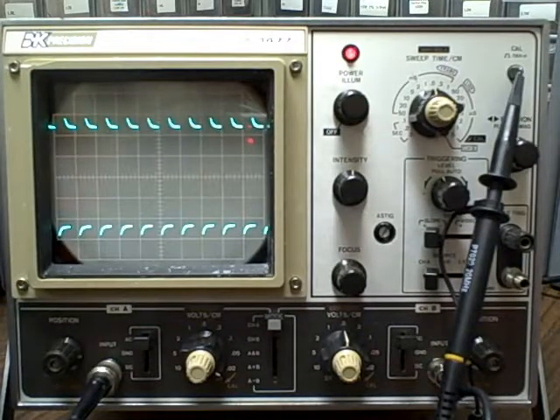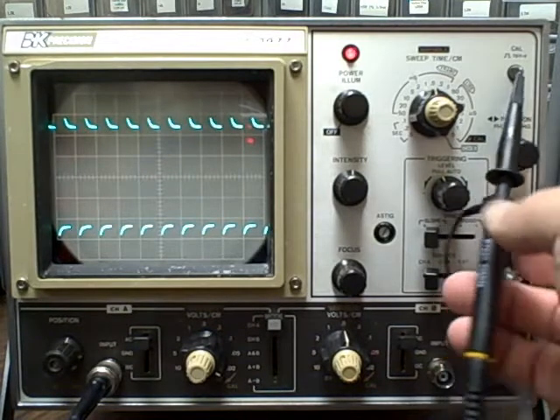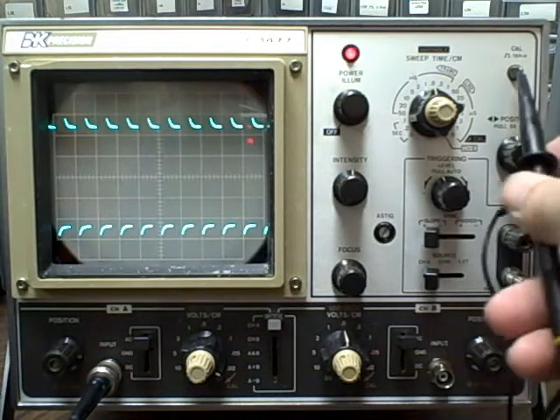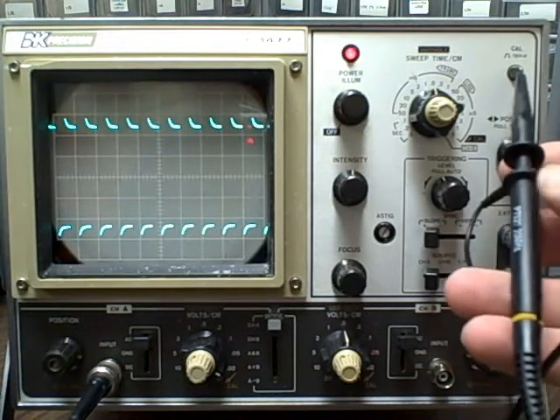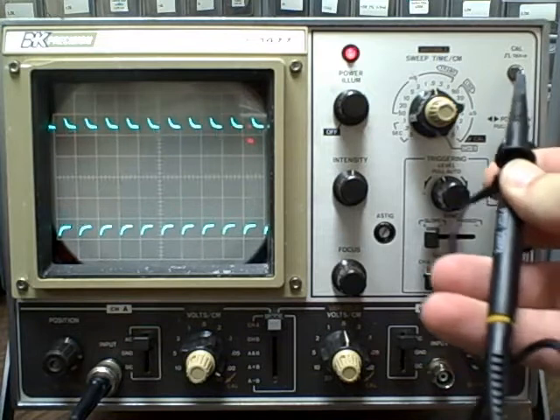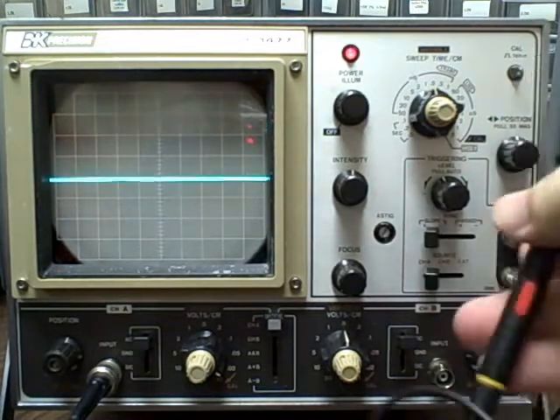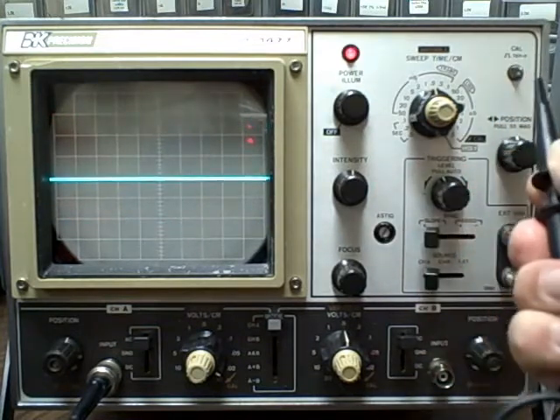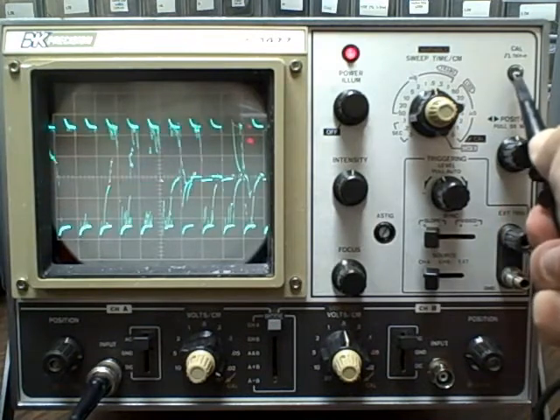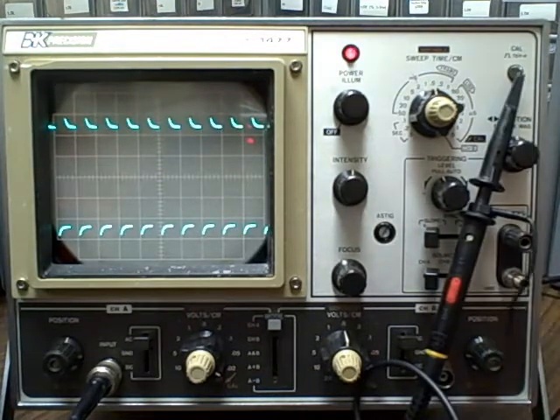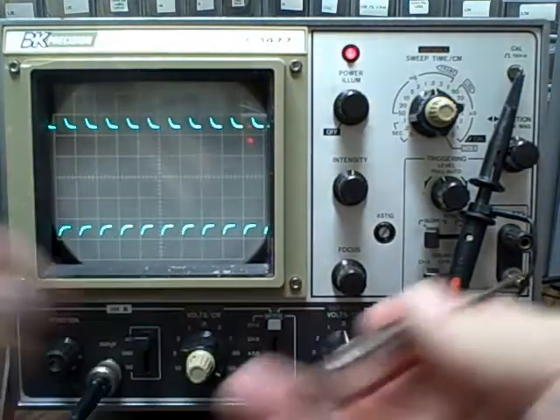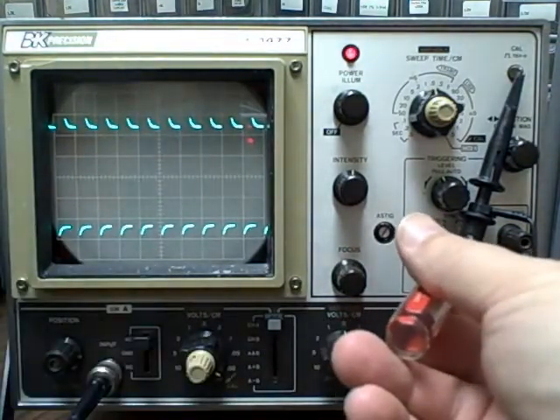Okay, we have a 20 megahertz probe, one of the new probes that will come with the scope, and we've connected it up to the probe adjustment test point, and we're going to go ahead and calibrate this probe and show you how that's done. Connect it so it's easy to get to the screw here.